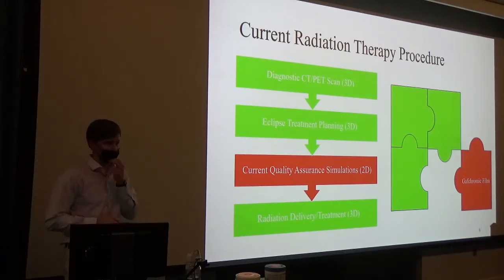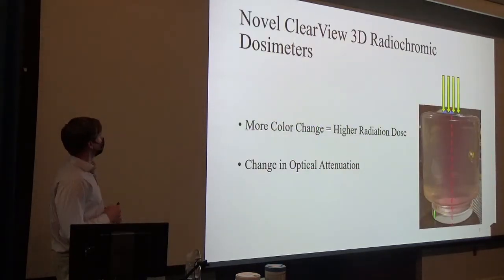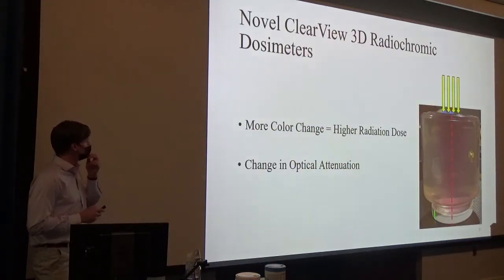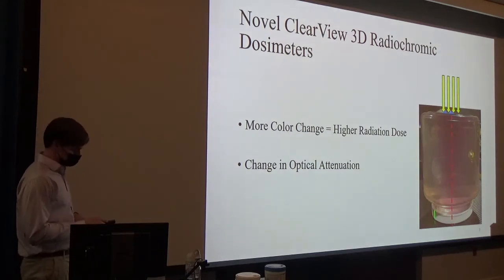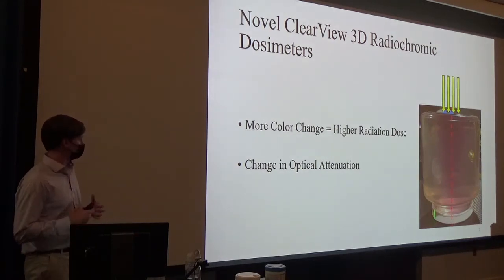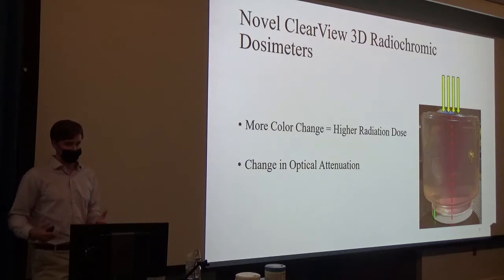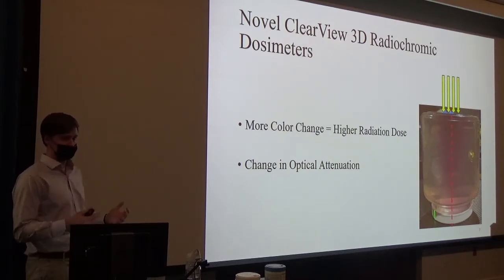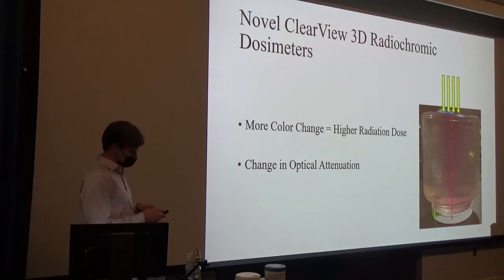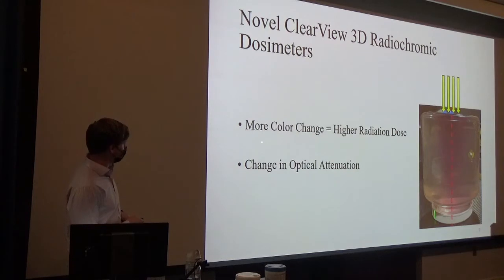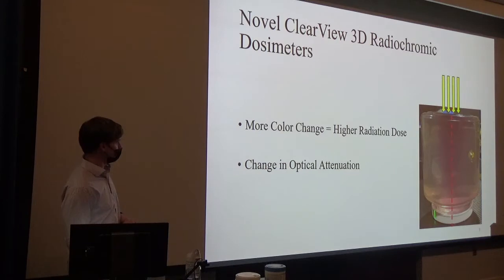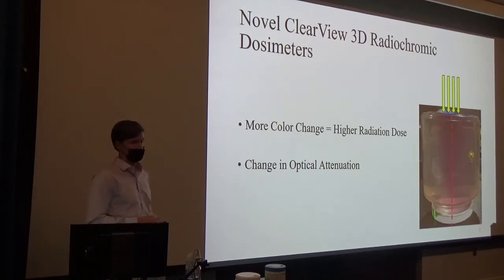That's where my project looked to find a solution. Our solution came in the Clearview 3D radiochromic dosimeter — pictured to the right. These work the same way as 2D radiochromic and gafchromic films, except installed into a gel that forms a volume. The radiation beam is sent down the central axis, and the more color change observed — which we call the change in optical attenuation — is associated with a higher radiation dose. The top is darker than the bottom, and the sides are almost clear, meaning little or no radiation reached those regions.